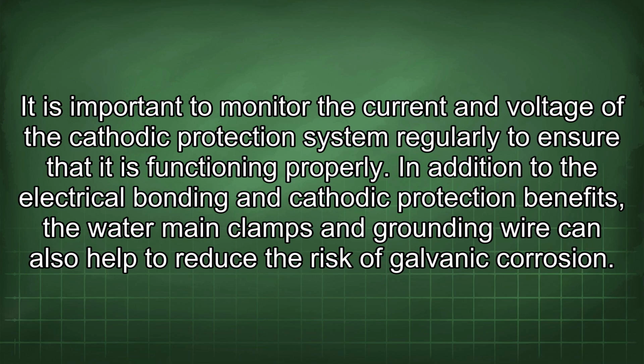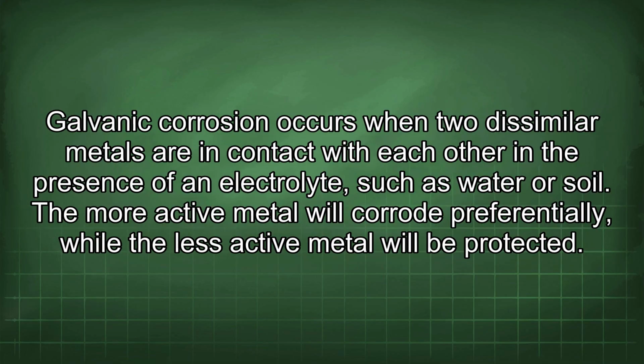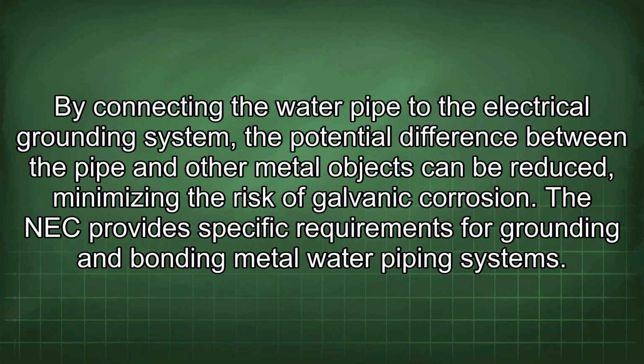In addition to the electrical bonding and cathodic protection benefits, the water main clamps and grounding wire can also help to reduce the risk of galvanic corrosion. Galvanic corrosion occurs when two dissimilar metals are in contact with each other in the presence of an electrolyte, such as water or soil. The more active metal will corrode preferentially, while the less active metal will be protected. By connecting the water pipe to the electrical grounding system, the potential difference between the pipe and other metal objects can be reduced, minimizing the risk of galvanic corrosion.